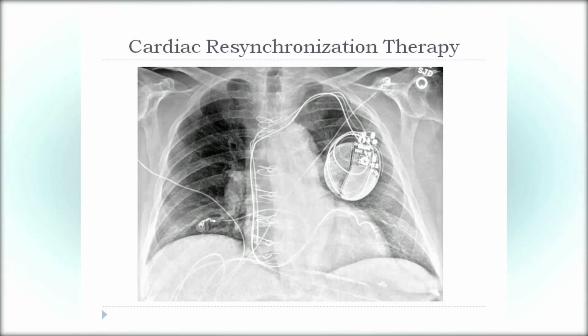You see, this is a bigger device. This is actually what's called an implantable defibrillator. This has a shocking electrode. This lead right here is a shocking electrode, which is bigger than a normal pacemaker lead. And this is a typical situation where if somebody goes too fast, this device has a capacitor and a battery. It can charge this and deliver a shock from this coil to stop the heart for milliseconds. And it shocks between here and the can, and then resets.